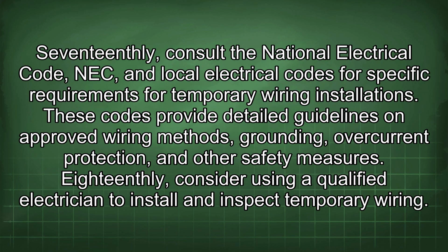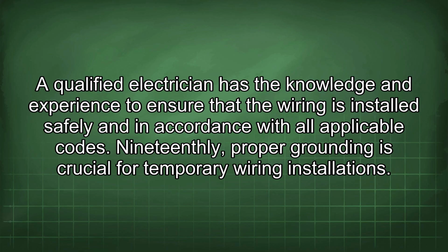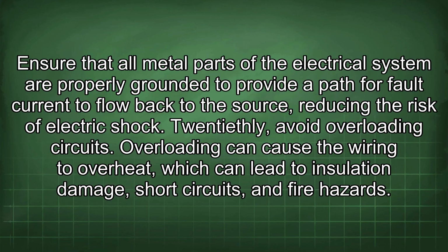17thly, consult the National Electrical Code (NEC) and local electrical codes for specific requirements for temporary wiring installations. These codes provide detailed guidelines on approved wiring methods, grounding, overcurrent protection, and other safety measures. 18thly, consider using a qualified electrician to install and inspect temporary wiring. A qualified electrician has the knowledge and experience to ensure that the wiring is installed safely and in accordance with all applicable codes. 19thly, proper grounding is crucial for temporary wiring installations. Ensure that all metal parts of the electrical system are properly grounded to provide a path for fault current to flow back to the source, reducing the risk of electric shock. 20thly, avoid overloading circuits.